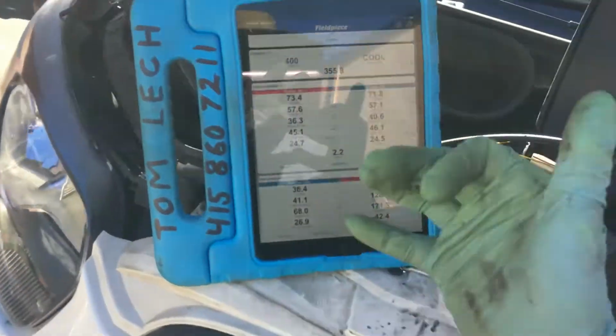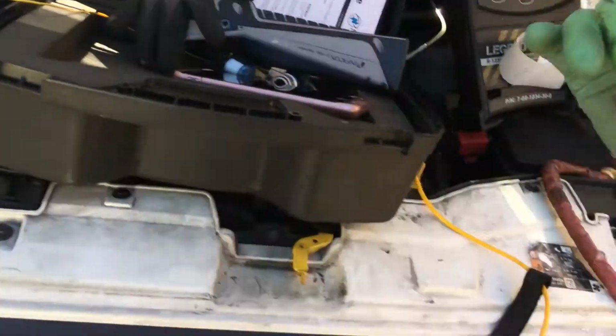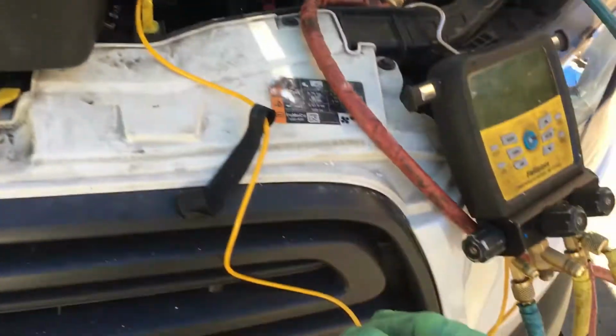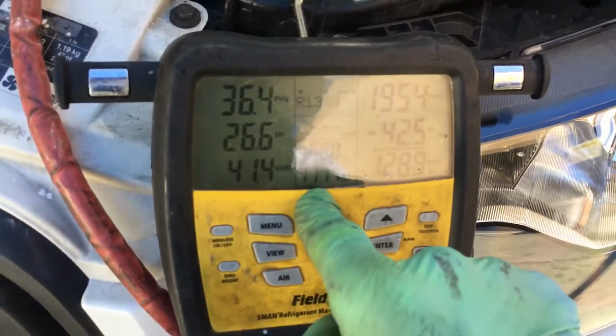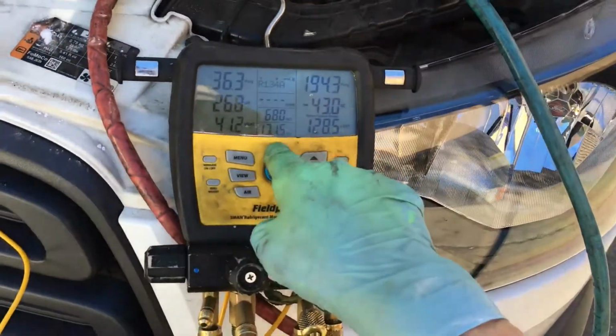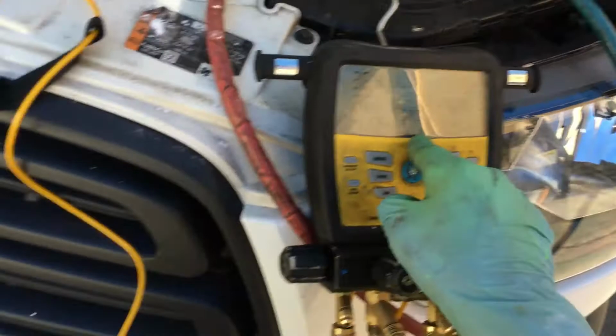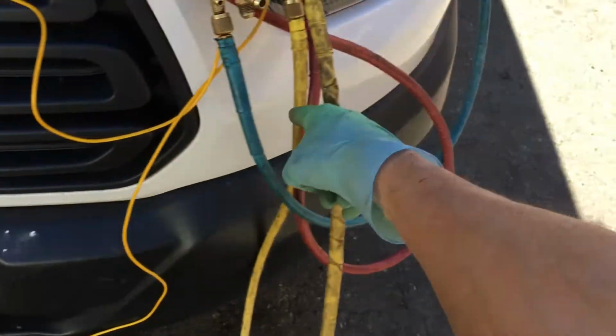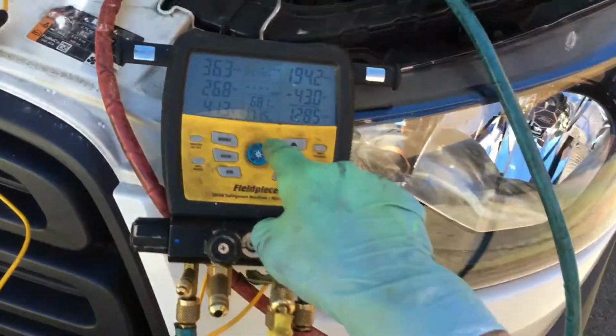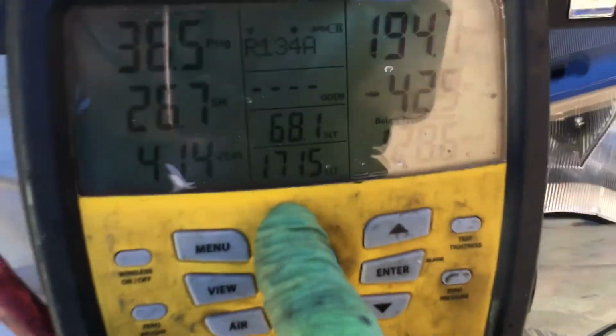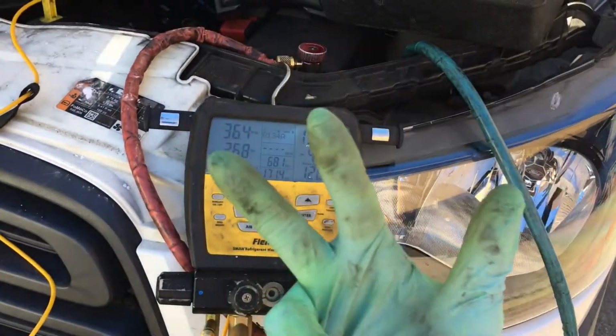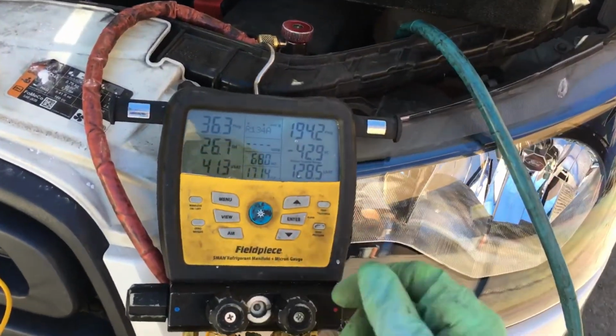All right, I'm going to put my phone down. I'm going to recover. Let's see what we recover out of this unit. And remember, this 171 degrees is the temperature of the gas discharge from the compressor about 5 feet away from the compressor, and it's this hot. All right, catch you on video number 3, do a recovery, and let's see what I take out.